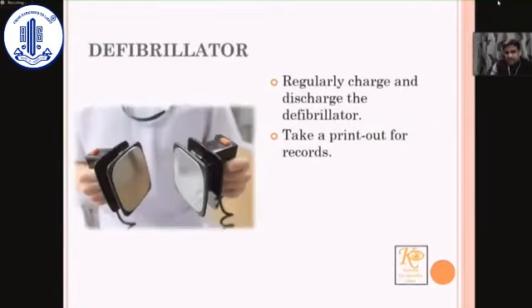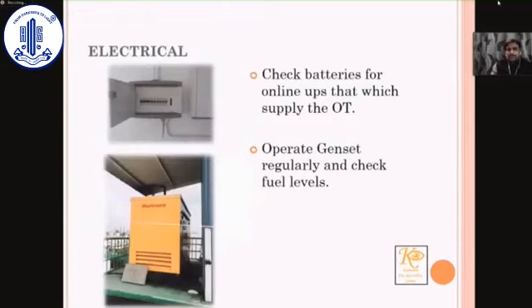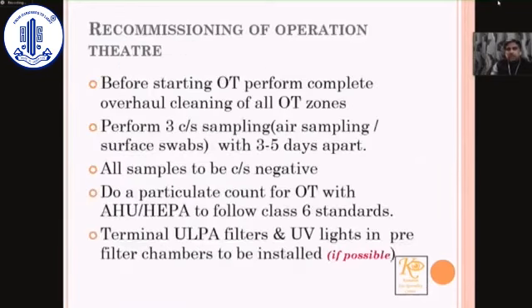The defibrillator has to be maintained as per your protocol. Charge them and discharge them regularly. This is a very important thing. Check the batteries of an online UPS and operate the gensets regularly, even during periods of shutdown. And these are salient features, the take-home message, during a recommissioning.